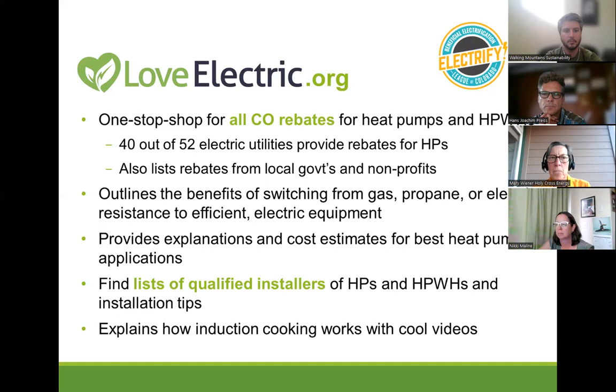Yeah, thanks. And I think that basically answered Mark's question about a 3,000 square foot home with a 15-year-old gas boiler and then wanting to have a backup. And you could leave the gas boiler left in place and control it to provide the hot water only when you need really low temperatures, right? So the heat pump would be your primary heat source. And just to make it very clear with our rebates, and I think same as you, Walking Mountains, right? The heat pump needs to be your primary heating source.